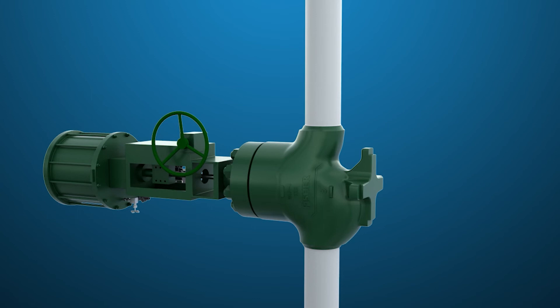With the high steam temperatures, class 5 shutoff using 800 pounds per inch of seat load and a bore seal is recommended.